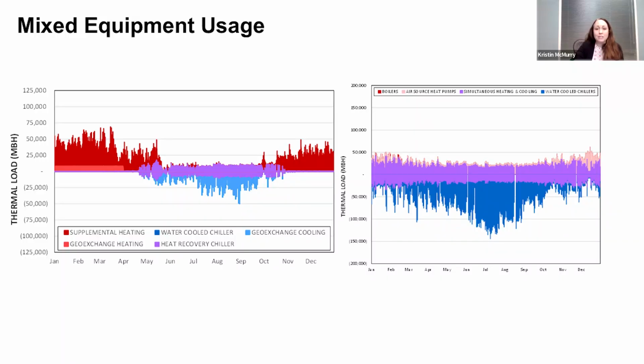But another client might say, I'm going to put in heat recovery chillers because I'm in North Carolina where it's nice and warm, and then the remainder of my load could be covered by air source heat pumps because it's never below 10 degrees there. And then they can use a pretty efficient system with water-cooled chillers for the remainder. So the solution is really very rarely one single technology, it's going to be a mix most of the time.